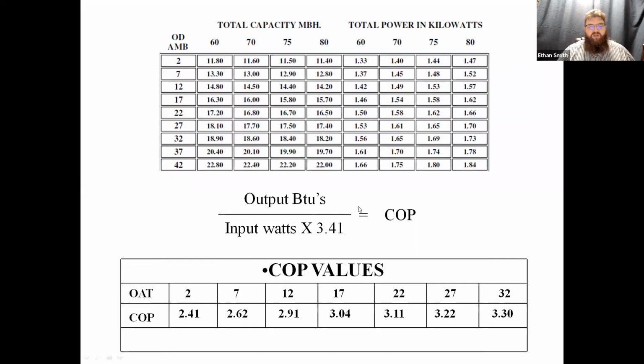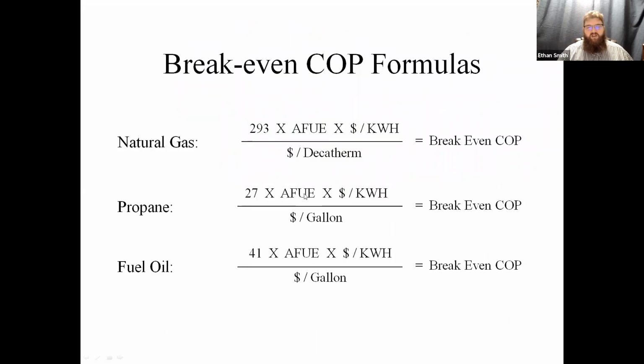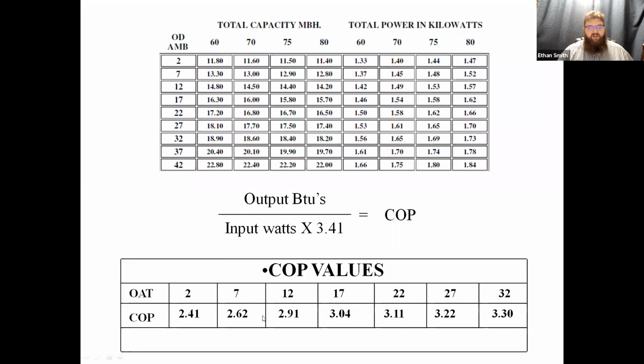Okay. What you would then do is take your COP from this calculation and find your outdoor temperature that closely corresponded to that COP. Then you would use that temperature as your balance point in your control system. So you would set that temperature as your compressor lockout temperature in the modern controls is how we do that. Any questions about that, guys?